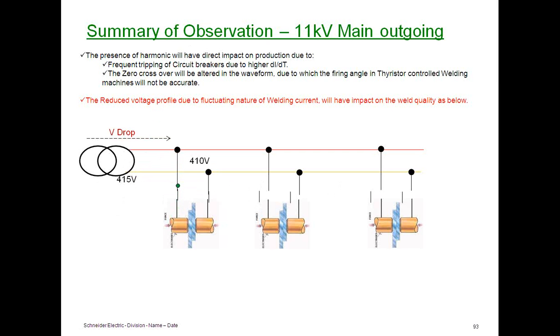And let's say the second welder is on. Let's say the drop is again a 10 volt drop. So on and so forth. That means if you assume the last welding machine comes on, it will operate at very low voltage. This low voltage is because of the natural drop occurring across the winding and the corresponding cables.